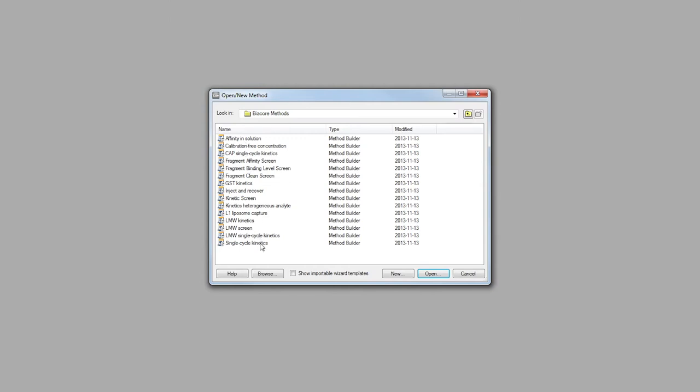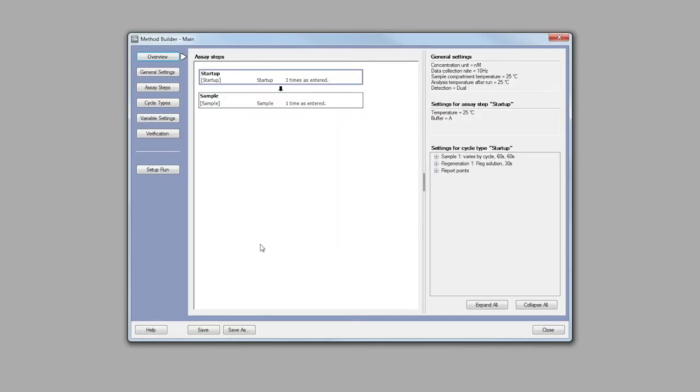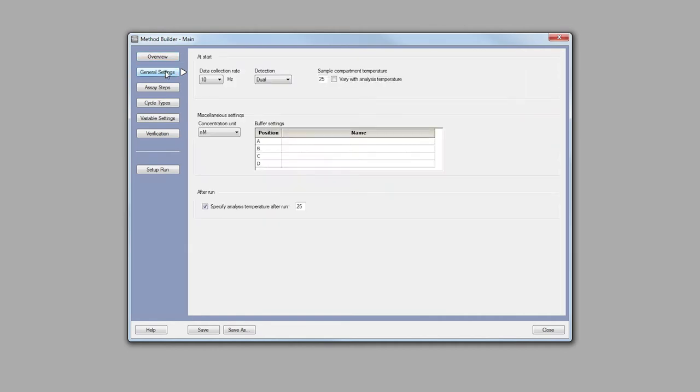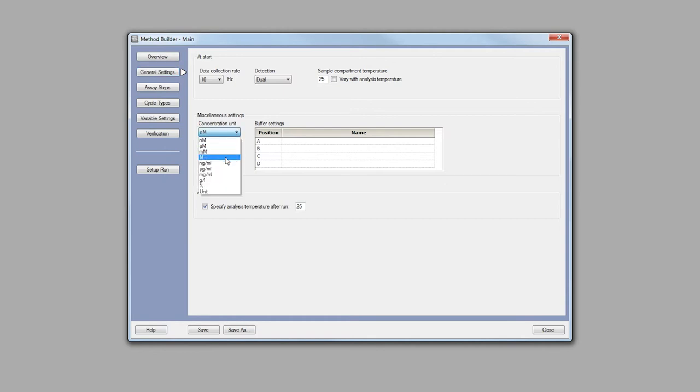Select single cycle kinetics and open. In the method overview, the start-up and sample assay steps are displayed. Moving down the left-hand panel, general settings are selected where data collection rate, detection path, concentration and buffer settings can be specified.